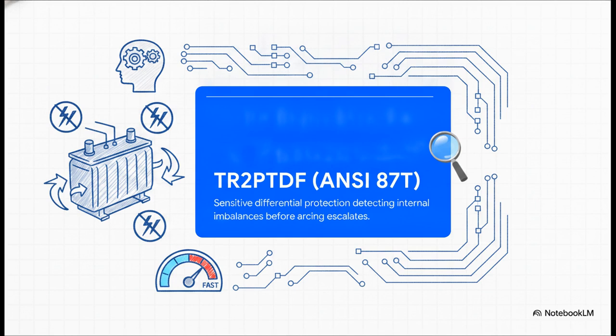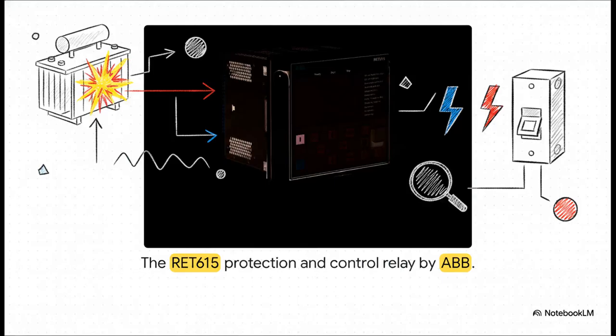It zeroes in on exactly what's happening inside that tank and completely ignores any outside grid issues. It is the fastest, most selective way to catch these internal faults. This specific software function actually lives inside purpose-built digital protection and control relays like the ABB RET615. Think of this device sitting in the substation as a high-speed computer with exactly one job. It constantly watches the currents, and the split second it detects the mathematical signature of an internal imbalance, it commands the massive physical breakers to trip instantly. It completely isolates the transformer from the network before our proverbial pressure cooker has a chance to explode.